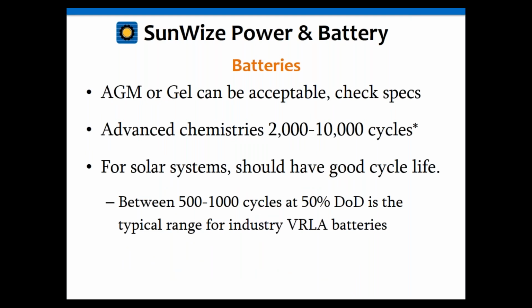Most batteries nowadays are AGM or gel. You don't see a whole lot of wet batteries anymore, as they require a lot more maintenance than gel and AGM batteries. But because of that, the gel and AGM batteries require a little more sophisticated charging. You don't want to overcharge or undercharge them. Flooded, wet batteries can be a little more forgiving in that area, whereas AGM and gels aren't. But both AGMs and gels, depending on the manufacturer and technology, are pretty much 50-50 in terms of acceptability in these systems.